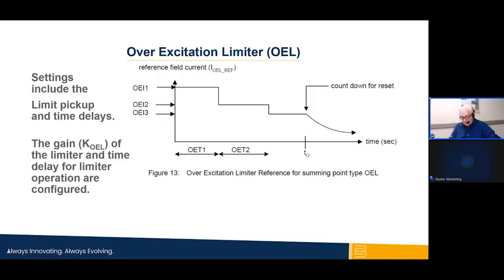We must distinguish between an overexcitation limiter, again, OEL, and an overexcitation protection, OEP, device. An OEL acts through the voltage regulator to reduce and maintain field current within the capability of the field winding. The OEP serves to remove the voltage regulator from service or to trip the generator offline when employed with an OEL. Properly coordinated, the OEP serves as a backup to the OEL, to ensure that the OEL and OEP characteristics coordinate properly, or let's say they do not cross each other.